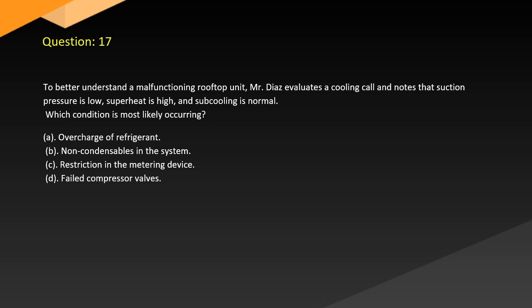Question 17. To better understand a malfunctioning rooftop unit, Mr. Diaz evaluates a cooling call and notes that suction pressure is low, superheat is high, and subcooling is normal. Which condition is most likely occurring? A. Overcharge of refrigerant. B. Non-condensables in the system. C. Restriction in the metering device. D. Failed compressor valves.